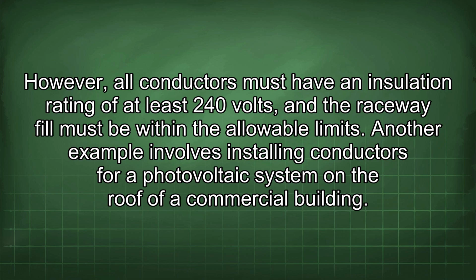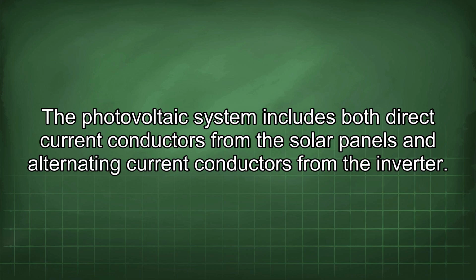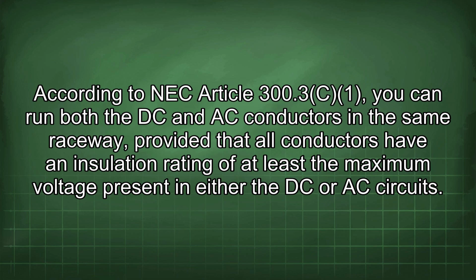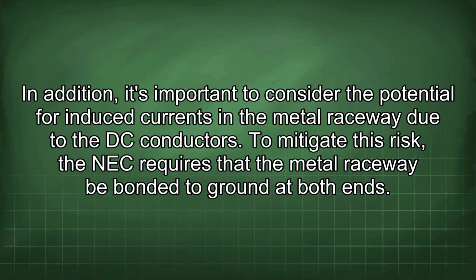Another example involves installing conductors for a photovoltaic system on the roof of a commercial building. The photovoltaic system includes both direct current conductors from the solar panels and alternating current conductors from the inverter. According to NEC Article 300.3, you can run both the DC and AC conductors in the same raceway provided that all conductors have an insulation rating of at least the maximum voltage present in either the DC or AC circuits. In addition, it's important to consider the potential for induced currents in the metal raceway due to the DC conductors. To mitigate this risk, the NEC requires that the metal raceway be bonded to ground at both ends.